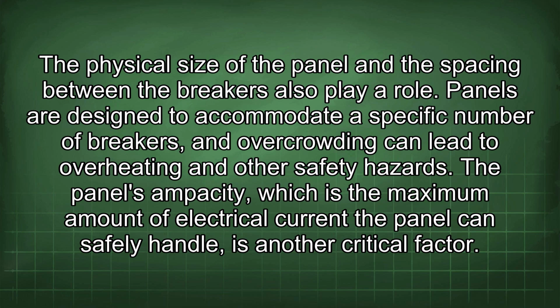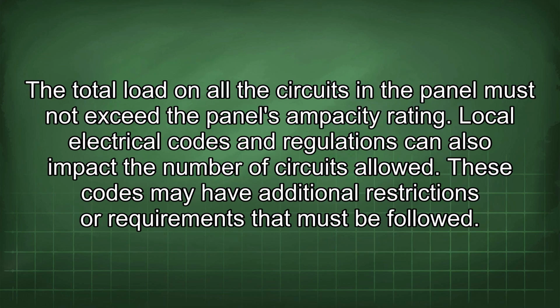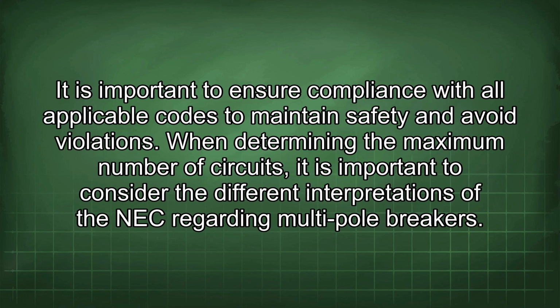Panels are designed to accommodate a specific number of breakers, and overcrowding can lead to overheating and other safety hazards. The panel's ampacity, which is the maximum amount of electrical current the panel can safely handle, is another critical factor. The total load on all the circuits in the panel must not exceed the panel's ampacity rating. Local electrical codes and regulations can also impact the number of circuits allowed. These codes may have additional restrictions or requirements that must be followed. It is important to ensure compliance with all applicable codes to maintain safety and avoid violations.